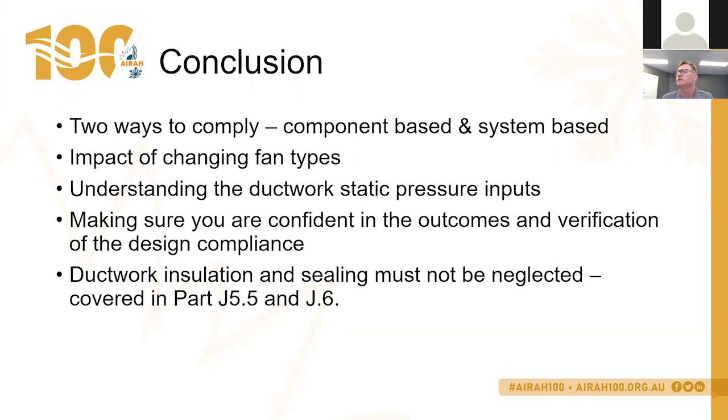Should a DX coil in a ducted system be taken into account when looking at the coil pressure drop? Yes. In reality, flexible ducts are not laid straight due to site constraints, etc. Is there a correction factor? No, there is not.